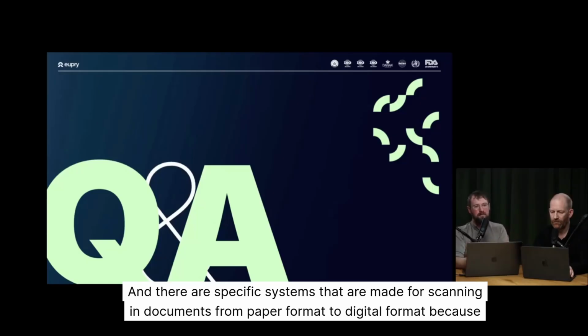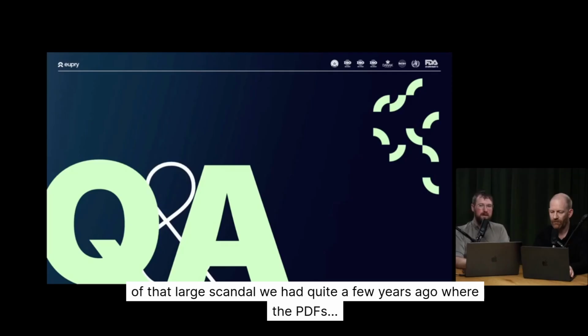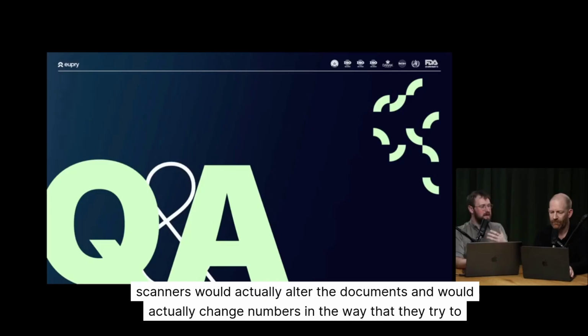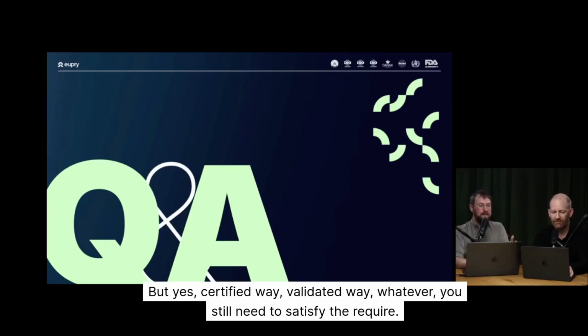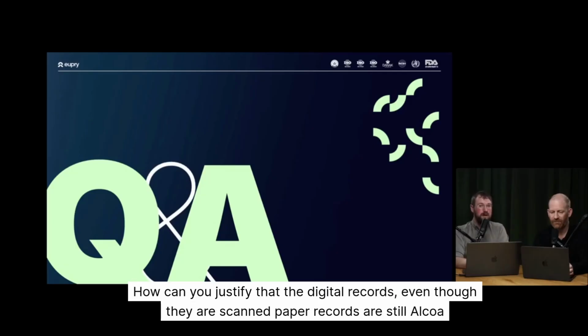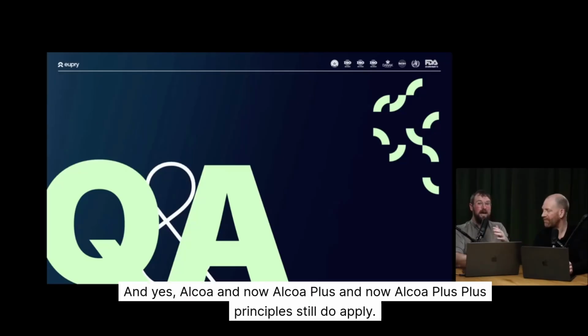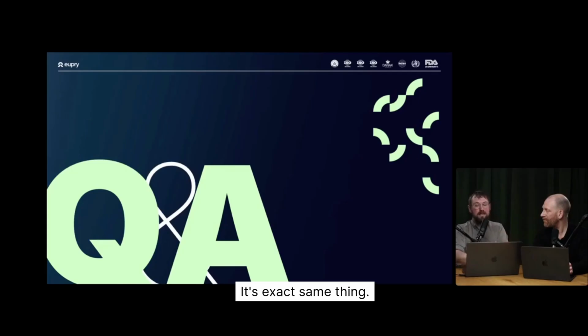that are made for scanning in documents from paper format to digital format because of that large scandal we had quite a few years ago, where the PDF scanners would actually alter the documents and would actually change numbers in the way that they try to memory optimize. But yes, certified way, validated way, whatever, you still need to satisfy the requirement. How can you justify that the digital records, even though they are scanned paper records, are still ALCOA applicable? And yes, ALCOA, and now ALCOA Plus, and now ALCOA Plus Plus principles still do apply. It's the exact same thing.